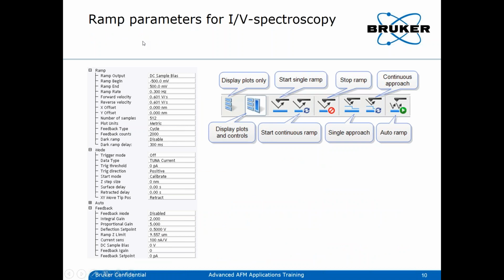These are the ramp parameters. If you go to the ramp mode for IV spectroscopy, at first the ramp output is not the Z height or the height sensor, but in this case the sample bias. You can set up your begin and end potential and how fast you would like to run it. Then you can select if you want a single ramp or a continuous ramp, if you want to stop the ramping or have a continuous approach, or, for instance, if you want more than one IV curve, you can go to the auto ramp and have it automatically set up a small matrix where it would run the IV curves.